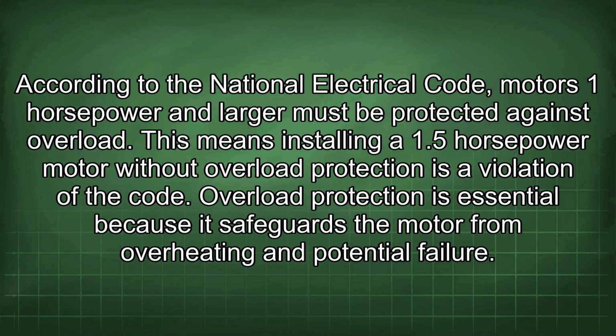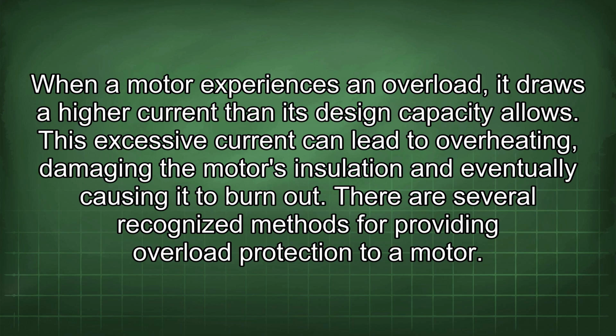According to the National Electrical Code, motors 1 horsepower and larger must be protected against overload. This means installing a 1.5 horsepower motor without overload protection is a violation of the code. Overload protection is essential because it safeguards the motor from overheating and potential failure. When a motor experiences an overload, it draws a higher current than its design capacity allows. This excessive current can lead to overheating, damaging the motor's insulation and eventually causing it to burn out.